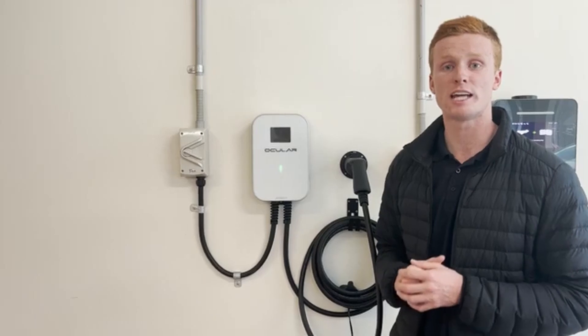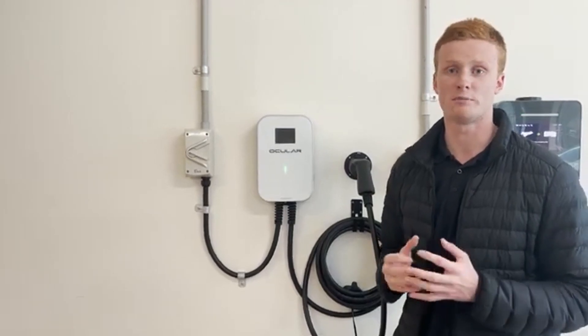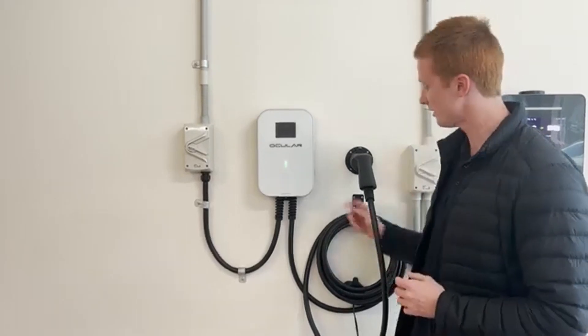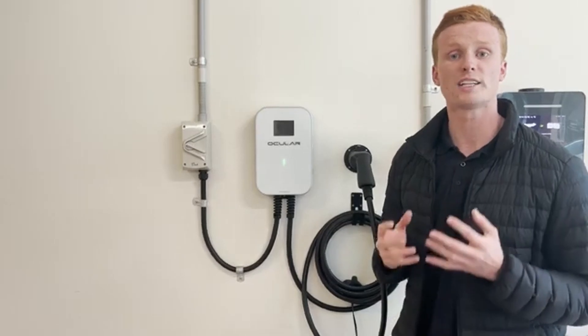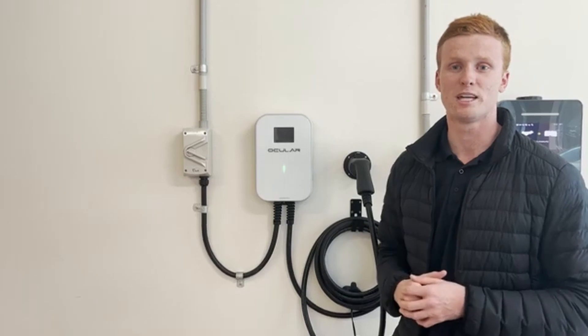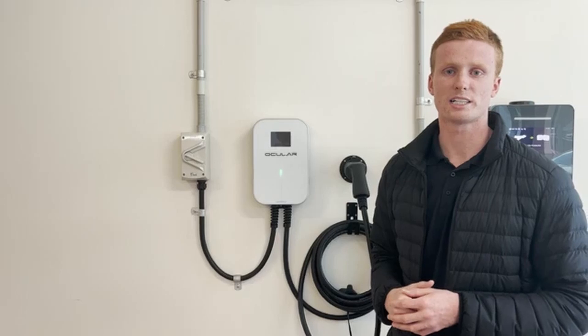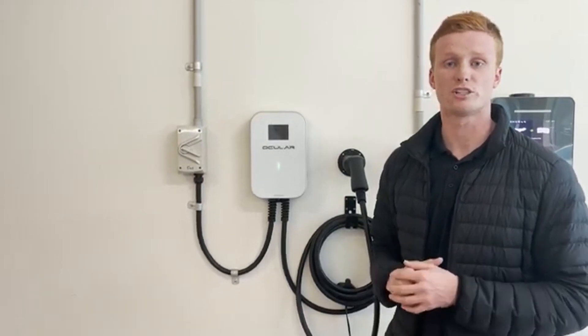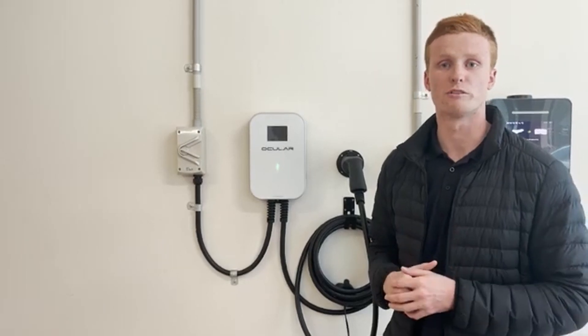If you have the OCULAR LTE basic charging station, this comes at a default of 8 amps, so you'll need to press the button on the side of the charging station to operate it to your desired speed. If you have the OCULAR LTE Plus charging station, this comes with a smart Bluetooth app called the EVSE Master. Before you leave the site, work with the customer to install it on their phone, as it allows them to down-rate and upgrade the charging station, schedule charging sessions, and monitor and track all their reports.